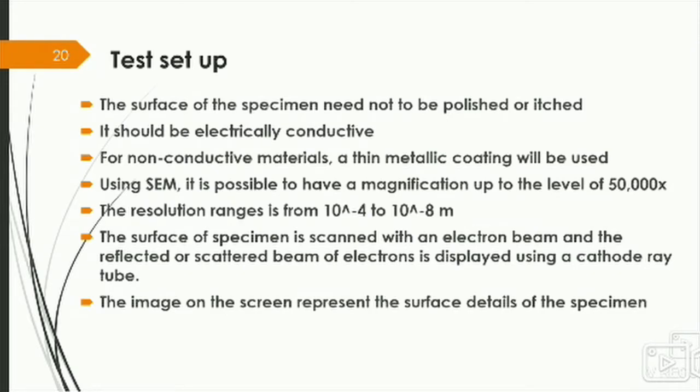The specimens used in this microscope have some specifications, that is, it need not be polished or etched, but at the same time it should be electrically conductive. If you are using a non-conductive material as the specimen, a thin layer of metallic coating will be applied on that specimen to make it electrically conductive.